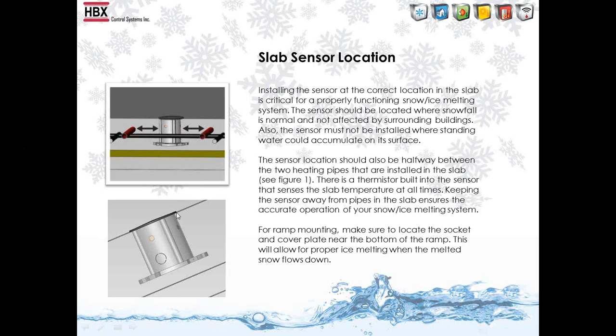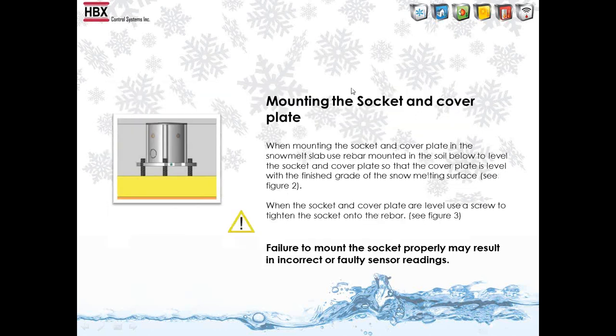We want you to mount it so it's flush on the top. We don't want you to have it below grade, because water will just collect inside of it, and we don't need water to collect inside of it, because we can detect snow very, very accurately when it hits that sensor. We don't want water collecting on there, because we might see it as snow. For mounting, we have 4 mounting locations where you can put rebar in, so you can level this to grade. If you put insulation, put the sensor right on top of the insulation. Just make sure that you pop a hole through the bottom of that insulation so that you have proper drainage.